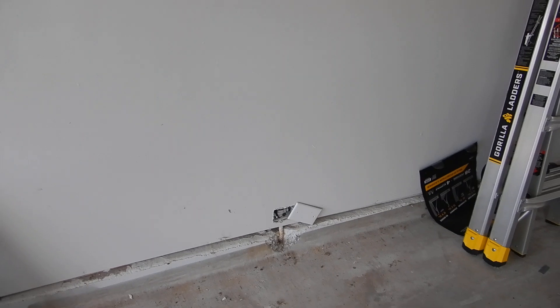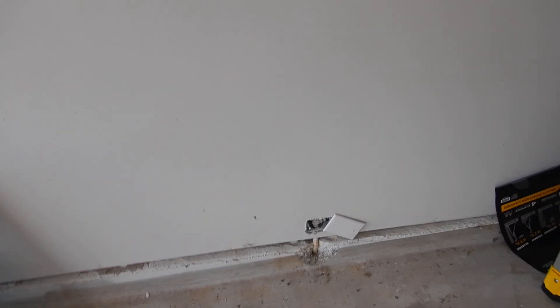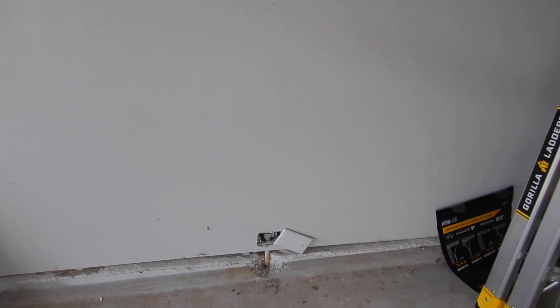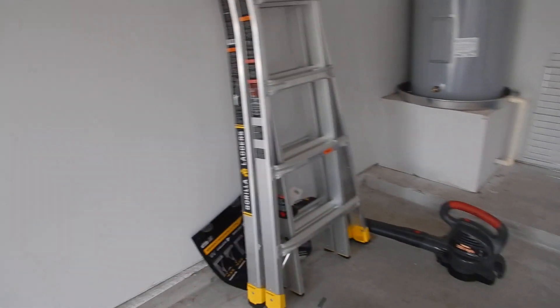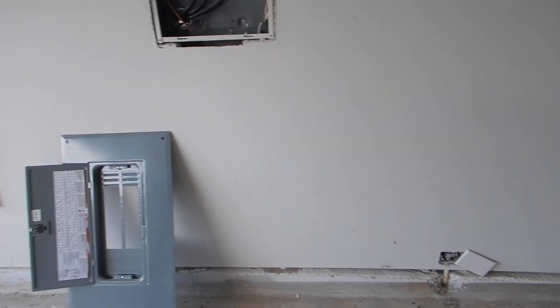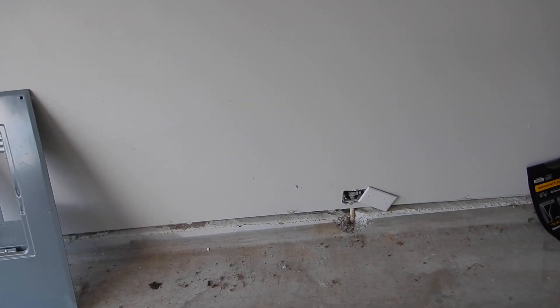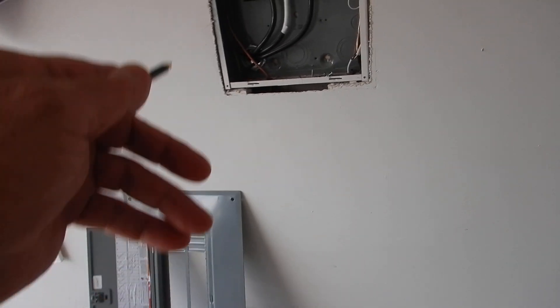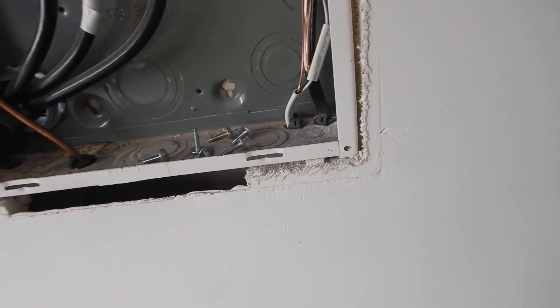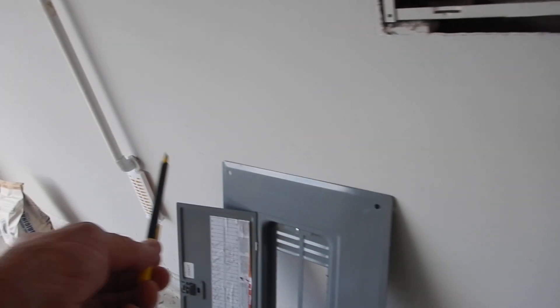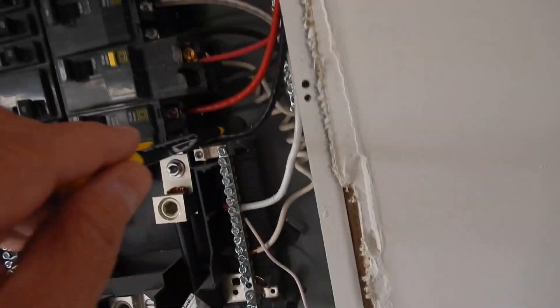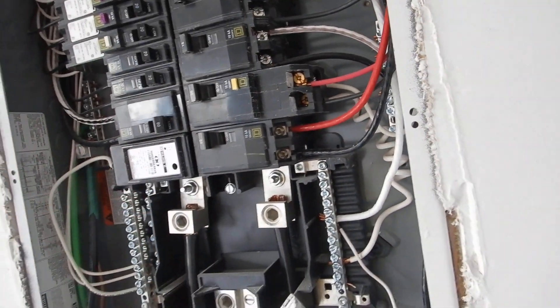I get it, an electrician's going to figure that out pretty fast. I think I figured it out. If I can figure it out, an electrician can figure it out. But what if you got a big freezer right here and he doesn't know where it's at? What if you got a cabinet over there? He's got to start looking. He knows it's going to be somewhere close, but that's an assumption. So it's supposed to be marked inside. We did not mark our bonding and our grounding location. We handwritten, did not seal all of our cabinets outside, that's undersized, that doesn't have a lockout on it.